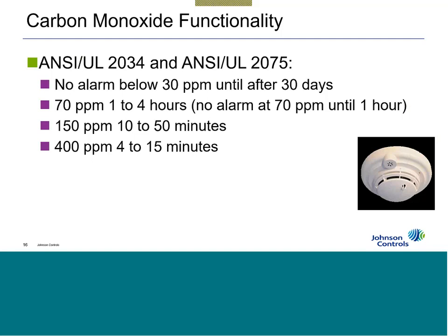If I pass that, now I clean the device out, clean the room out, put the device back in the room, inject 70 parts per million, and now the timing changes. I have to go into alarm no sooner than an hour, but no later than 4 hours. Pass that, clean out the room, do it again, inject 150 parts per million. Cannot go into alarm before 10 minutes, but not after 50. Clean out the room, do it again, 400 parts per million, not before 4 minutes, not after 15.